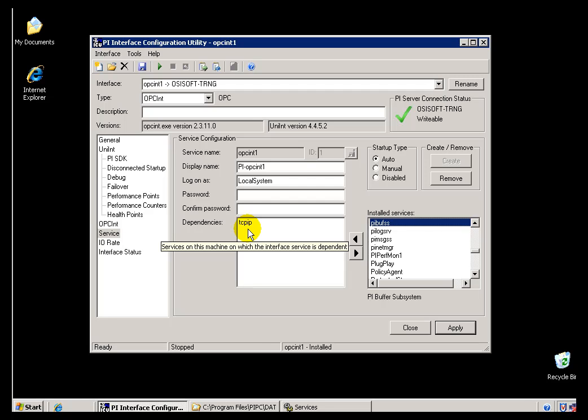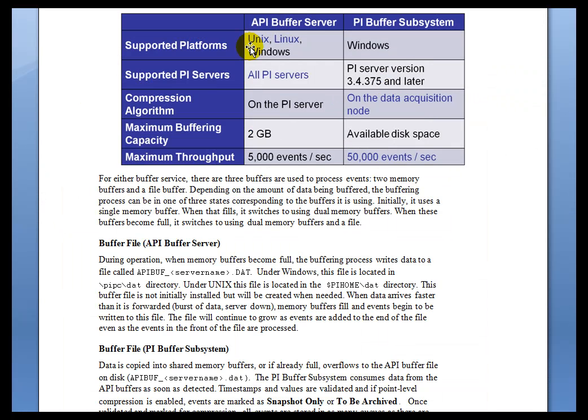You want to make sure that the services are started up in the right order — buffering first, and then the interfaces. Here's a chart that shows the two: the first is the API Buffer Server, which is the older of the technologies; the second is the PI Buffer Subsystem.